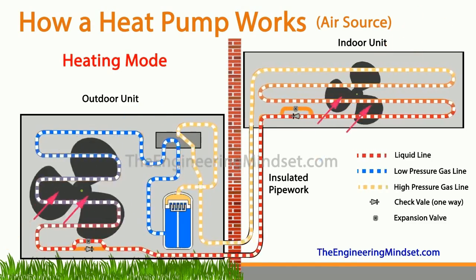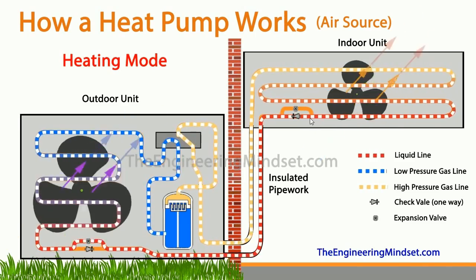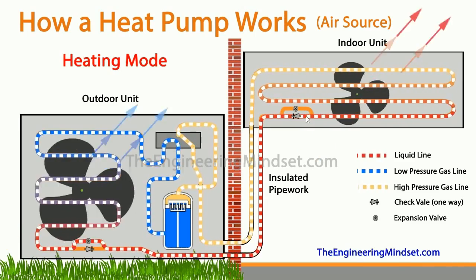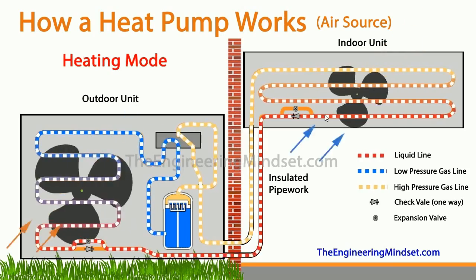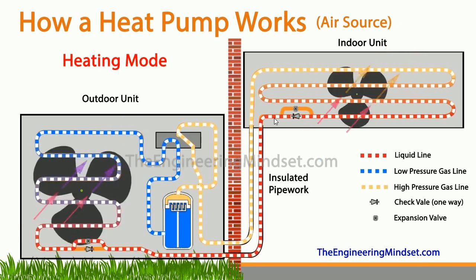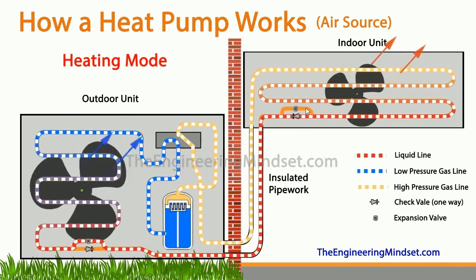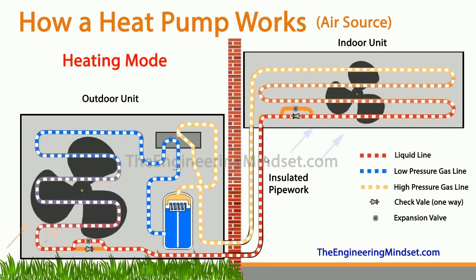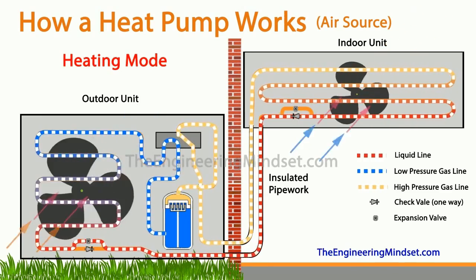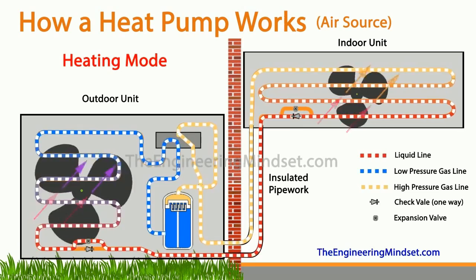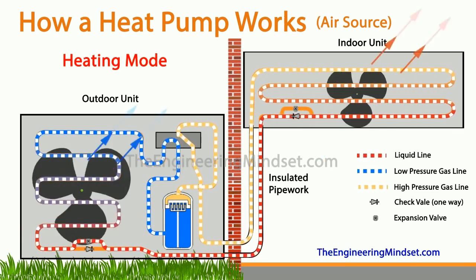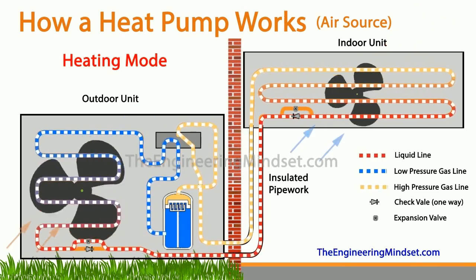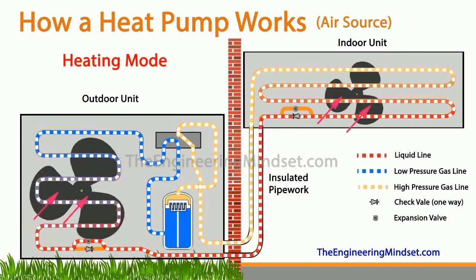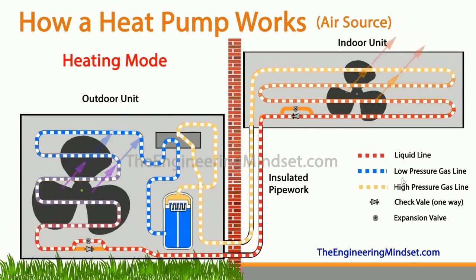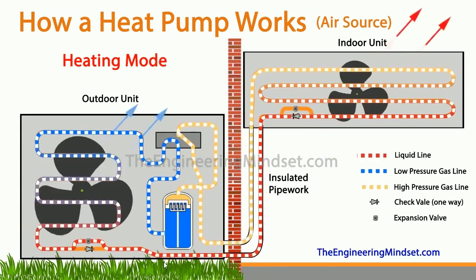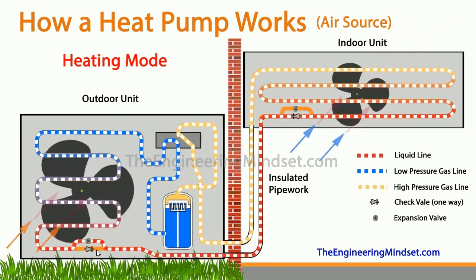By the time the refrigerant leaves the coil, you can see it comes along here and comes towards the check valve and expansion valve, and in this instance it's going to pass through the check valve because the expansion valve will not let it pass that way, so it will flow through here. So that refrigerant, as it's leaving the coil and has passed through the check valve, will leave there as a high pressure, medium temperature saturated liquid, and this flows along this liquid line straight down to the outdoor unit.